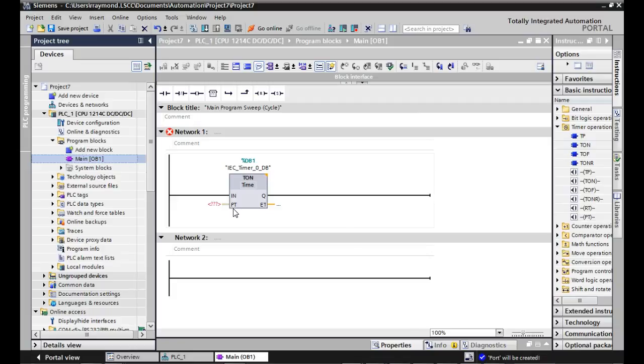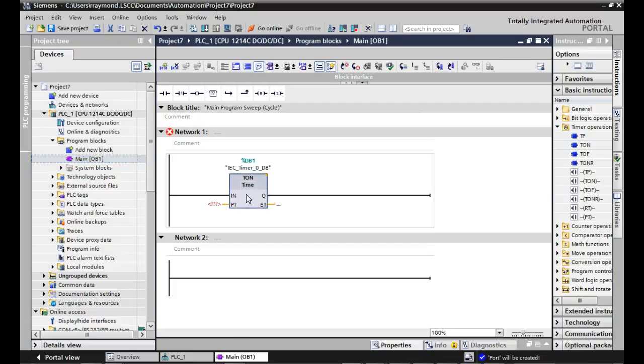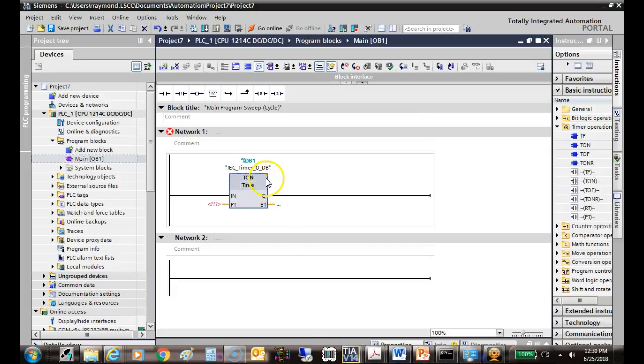Preset. By the way, what's neat about Allen Bradley, you can left click on any one of them, and then you can hit F1, and it's going to bring up everything about that block that you need to know. Hopefully. By the way, this guy doesn't have any options sometimes, but look what I can do here. I can see this little thing up here in the right-hand corner. Can you see that? I'm going to click that, and it brings up a scroll. And I can change this from an off-delay timer, on-delay timer, retentive timer without deleting it and dragging it out, which is pretty neat.